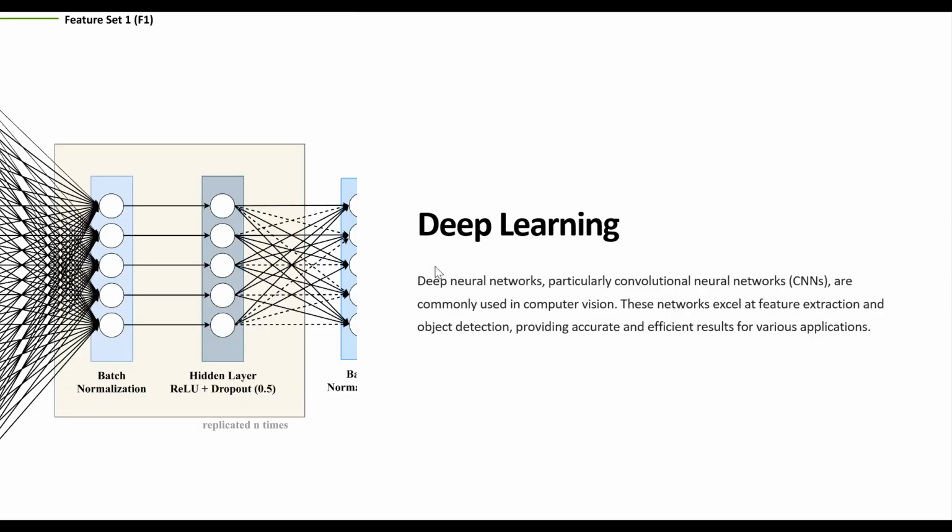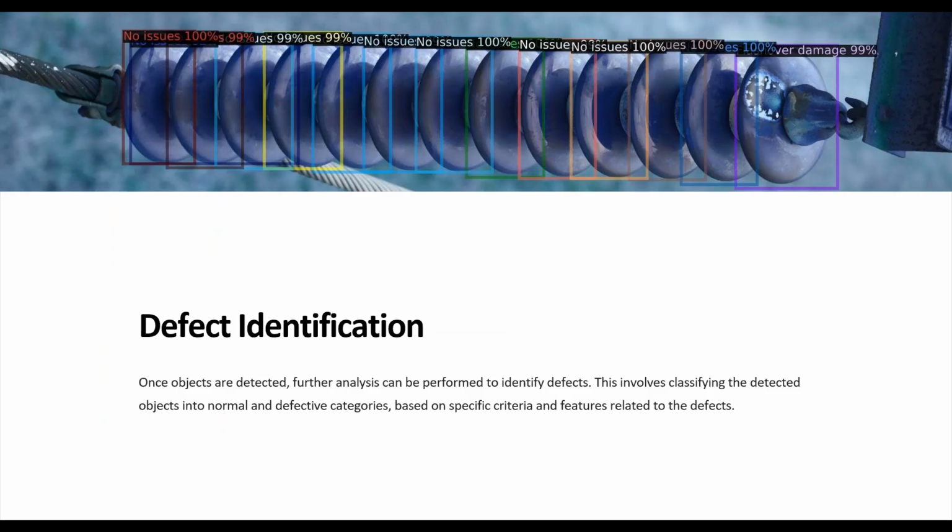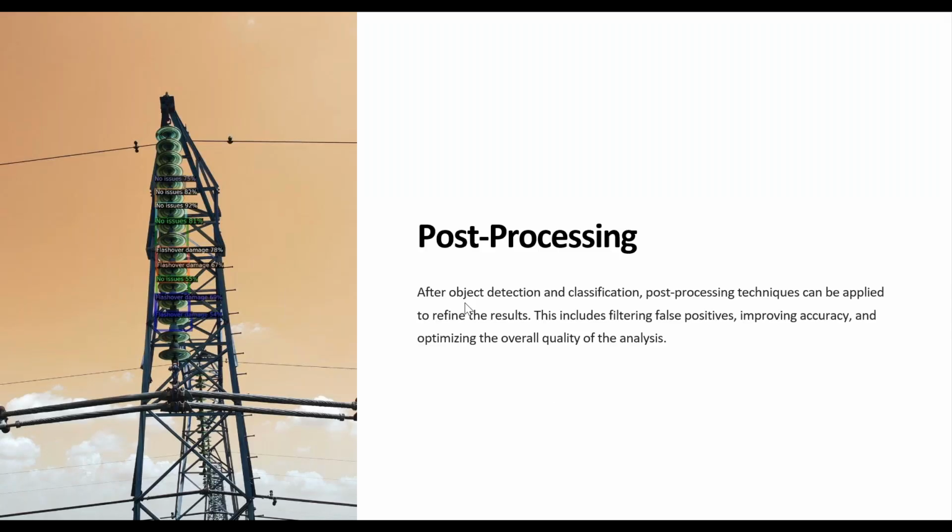There are multiple layers for the deep learning and how you get to analyzing pictures. So I'm just going to skim through this, and I have talked about these pictures when I showed some results there. In this picture, it's more visible to see the flash mark, and it does tell you you've got a flash mark, flashover damage here on this insulator. So that's now a result of that defect identification model using Fast CNN that you're developing.